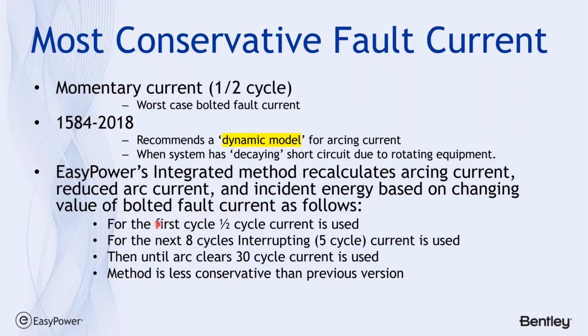And so what that means is for the first cycle of the fault, EasyPower will integrate using the half cycle value for available fault current. During the next 8 cycles, the tool will integrate the model for the 5 cycle value, or the interrupting current calculated for the bus. And if the arc lasts more than those 9 cycles, the arcing current will be calculated based upon the 30 cycle steady state current from the model. So it's agreed the method is less conservative than the previous value, and it will clear up some of the issues we had with lower current.